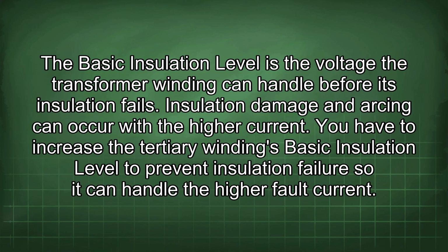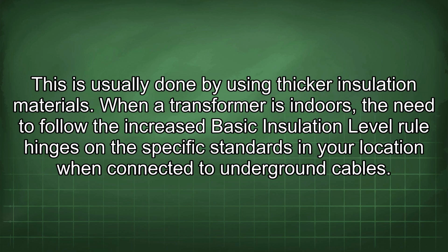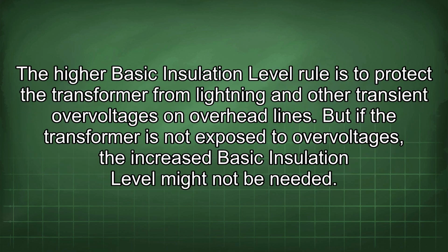The basic insulation level is the voltage the transformer winding can handle before its insulation fails. Insulation damage and arcing can occur with the higher current. You have to increase the tertiary winding's basic insulation level to prevent insulation failure so it can handle the higher fault current. This is usually done by using thicker insulation materials. When a transformer is indoors, the need to follow the increased basic insulation level rule hinges on the specific standards in your location when connected to underground cables. The higher basic insulation level rule is to protect the transformer from lightning and other transient overvoltages on overhead lines. But if the transformer is not exposed to overvoltages, the increased basic insulation level might not be needed.